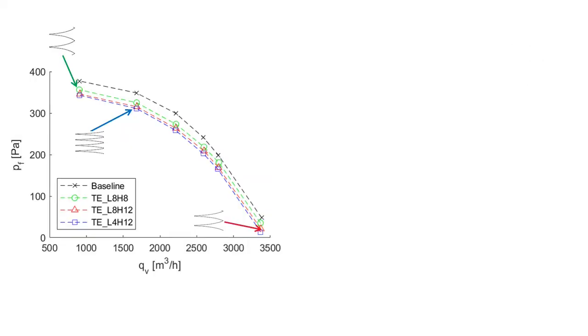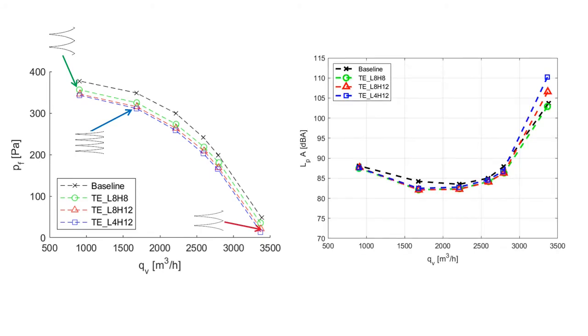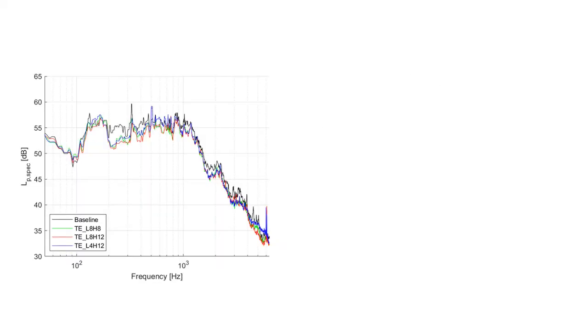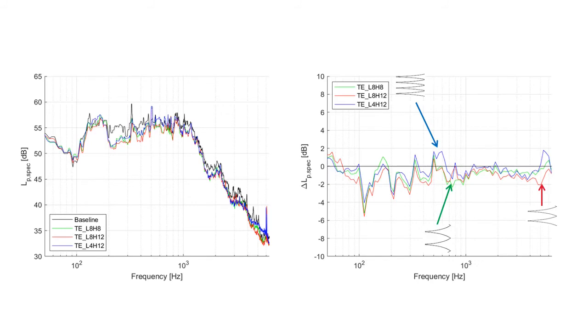Okay, let's move to trailing edge serrations. If we look at the fan curve, there's a pressure drop for all operating points. If we look at the specific noise, which accounts for these pressure losses, trailing edge serrations achieve a slight noise reduction. If we take a look at the noise spectra, this noise reduction is broadband. This is for all frequencies.